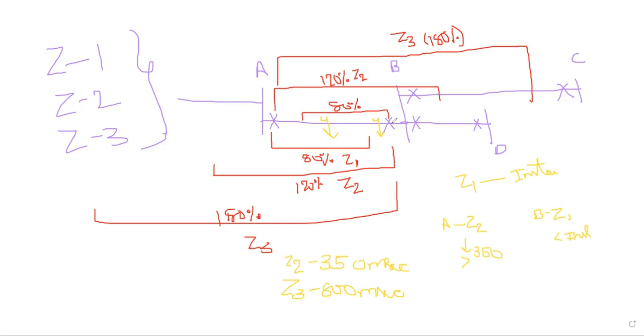To do this inter-tripping of the breakers, if one breaker is tripped, the other breaker has to trip. There are different types of schemes that we call permissive inter-trip schemes. One is the PUTT, POTT. These are some inter-trip schemes. DUTT and DCUB we are not using now because these are direct trippings, like U is underreach, O is overreach. What is underreach or overreach? I will explain. DUTT is a direct trip. Means if this breaker is tripped, this breaker will trip. That's it. No condition, nothing is there.